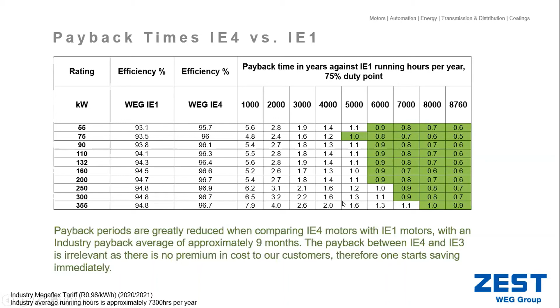We looked at running hours and the efficiency difference between a standard motor and an IE4. Doing the maths, we see payback starting from just over 6 months. If a motor runs more than 6 months, or closer to a full 12-month period running 24 hours a day, you will definitely get a payback. The cutoff point is around about 6 months.